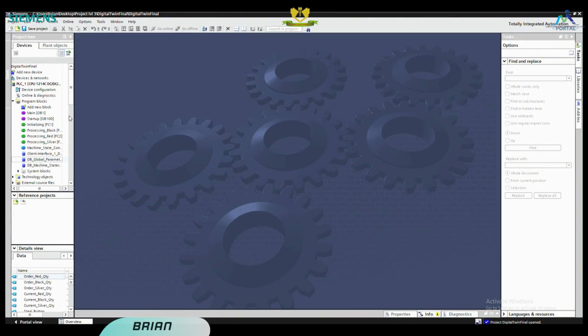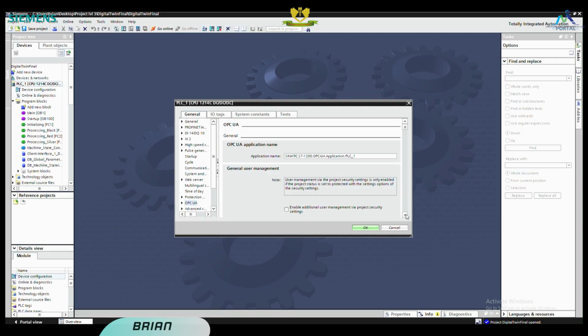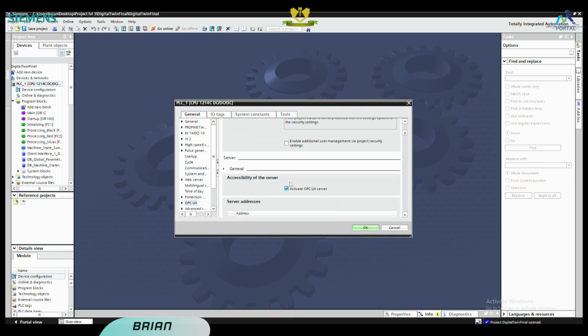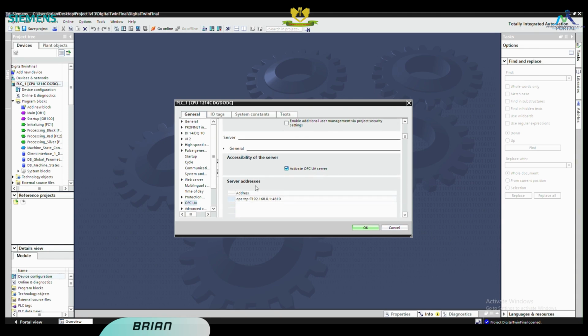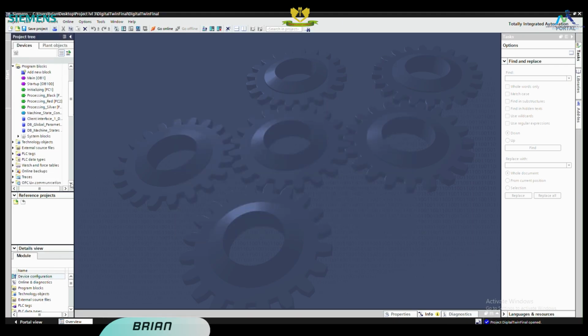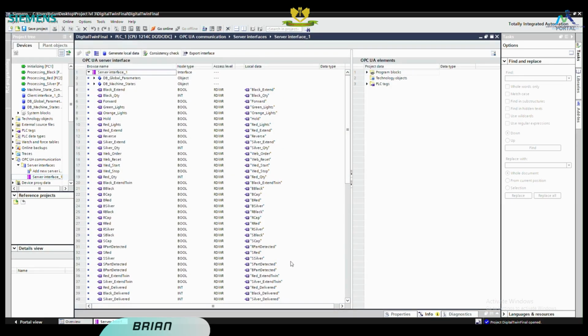Now, in our system, we use the S1200 PLC as our server, whereby to configure it, we had to activate the OPC-UA server to allow accessibility of the server, then set the server address, and thereafter we had to configure the server interface. The server interface allows communication with the external system, and it mostly defines the nodes by exposing tags, data blocks, and user-defined types, mostly that you want exposed.